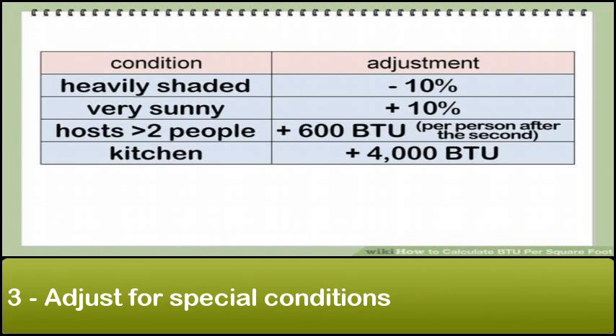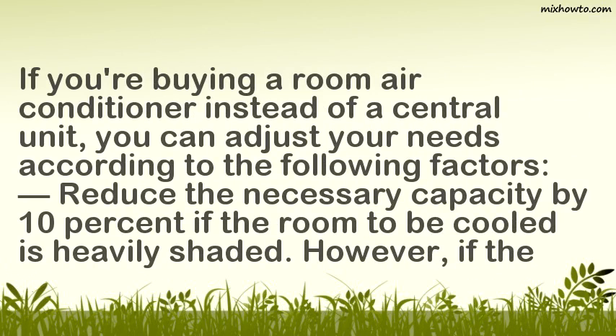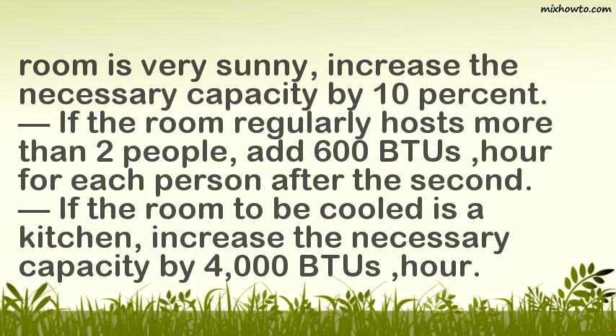Adjust for special conditions. If you're buying a room air conditioner instead of a central unit, you can adjust your needs according to the following factors: reduce the necessary capacity by 10% if the room to be cooled is heavily shaded; however, if the room is very sunny, increase the necessary capacity by 10%. If the room regularly hosts more than 2 people, add 600 BTUs for each person after the second. If the room to be cooled is a kitchen, increase the necessary capacity by 4,000 BTUs per hour.